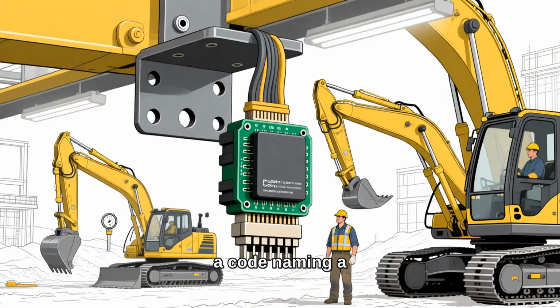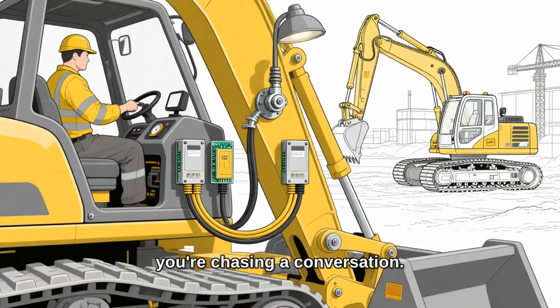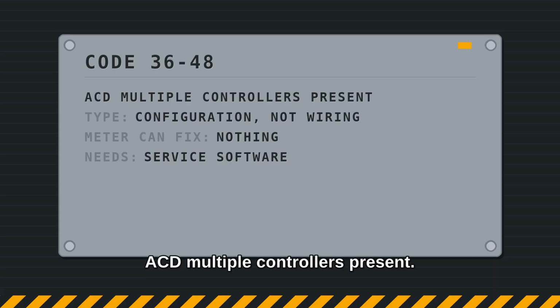Second trigger, a code naming a controller. 32.4 is ACS not communicating with Bobcat controller. Now you're not chasing a wire, you're chasing a conversation. Power, ground, and the network carrying it. Third, 3648, ACD multiple controllers present. That's a configuration problem and no amount of probing will fix it.